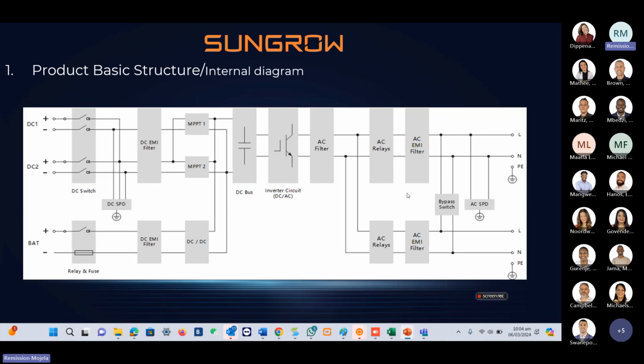So one other thing that Leonard mentioned is that we have a 10 millisecond changeover basically. So that 10 millisecond happens when grid falls off. Normally, when this system is connected to grid, the power that will be converted from the DC side, which is from the battery and the PV, goes through this AC relay, and then the AC EMI filter to the bypass, and then to the backup loads, and then to the grid and non-critical loads as well, so the grid loads that side.